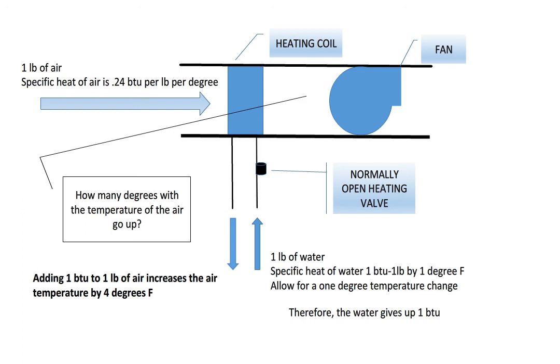It turns out that what we want is for the heat transfer to be linear. The equal percentage plug will bring the heat transfer into a linear relationship with the valve stroke and we gain control. For best control using hot or chilled water to heat or cool air, use an equal percentage plug. This is Norm Kristofferson. Thanks for watching.